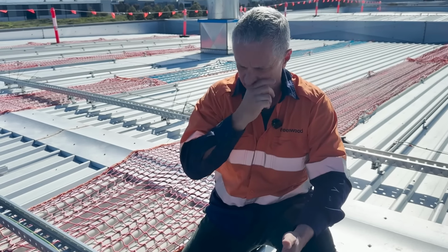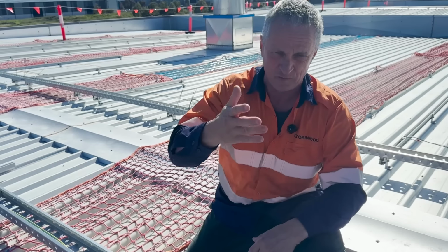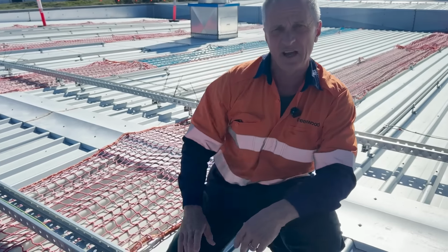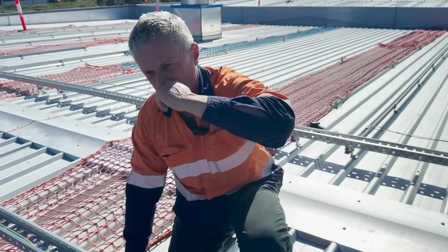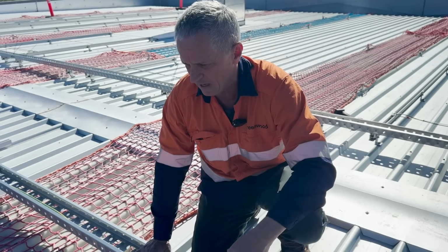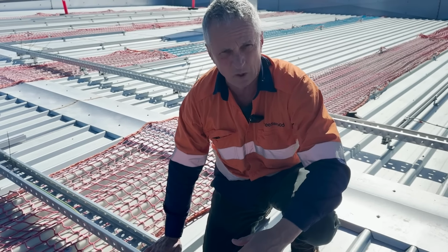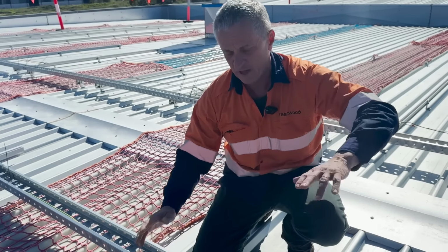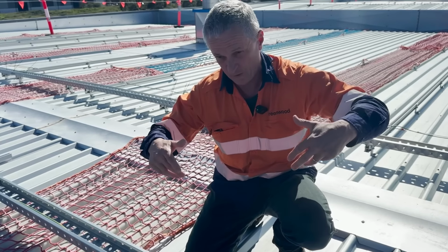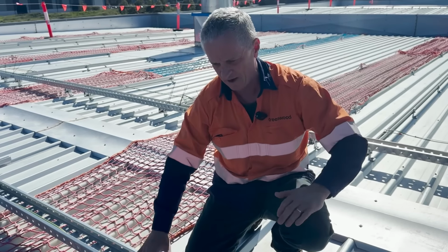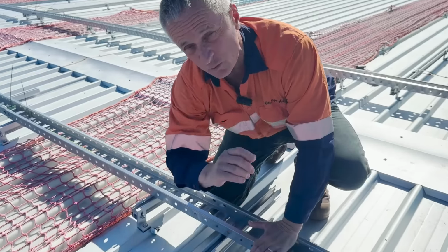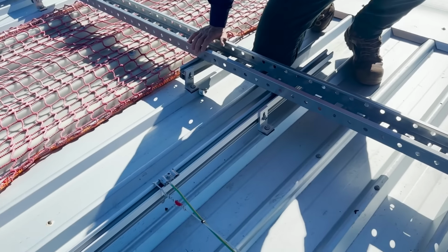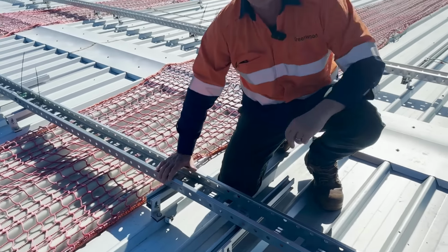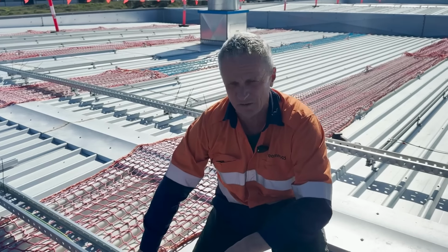So say for instance, because I know this one, a 110 kVA Sungrow, and you're using say 95mm red, white and blue, you'd be using a 25mm earth. And if you're using no string fusing in that particular case study scenario, this earth would have to be 25mm. So really, it's probably a good idea to use string fusing.